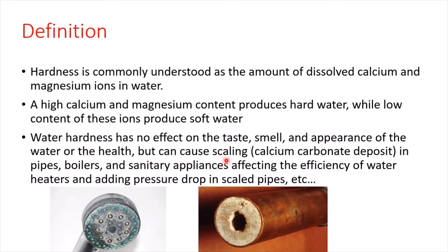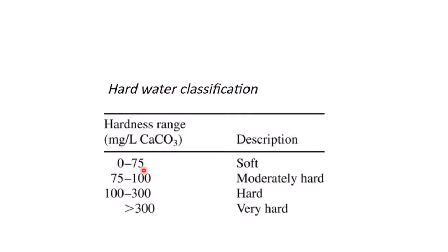The major problem with hard water is scaling. We will have a calcium carbonate deposit — as you can see in this picture — and this can occur in our pipes, boilers, and sanitary appliances within the house. This will affect the efficiency of water heaters and will add pressure drop within the scaled pipes.